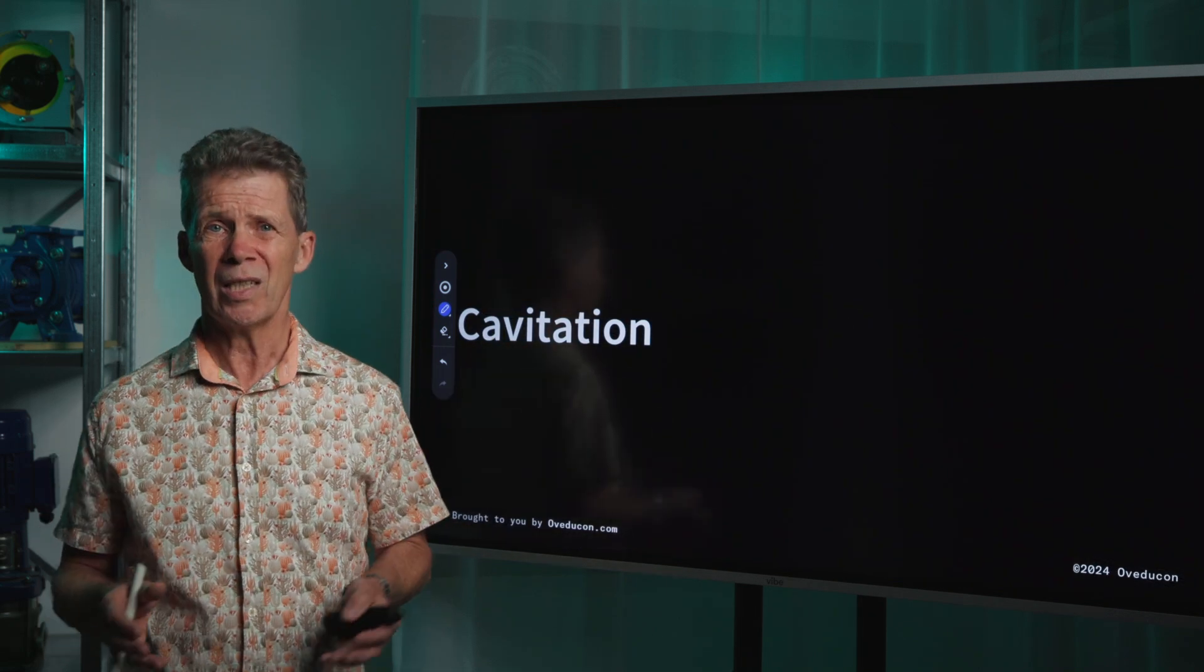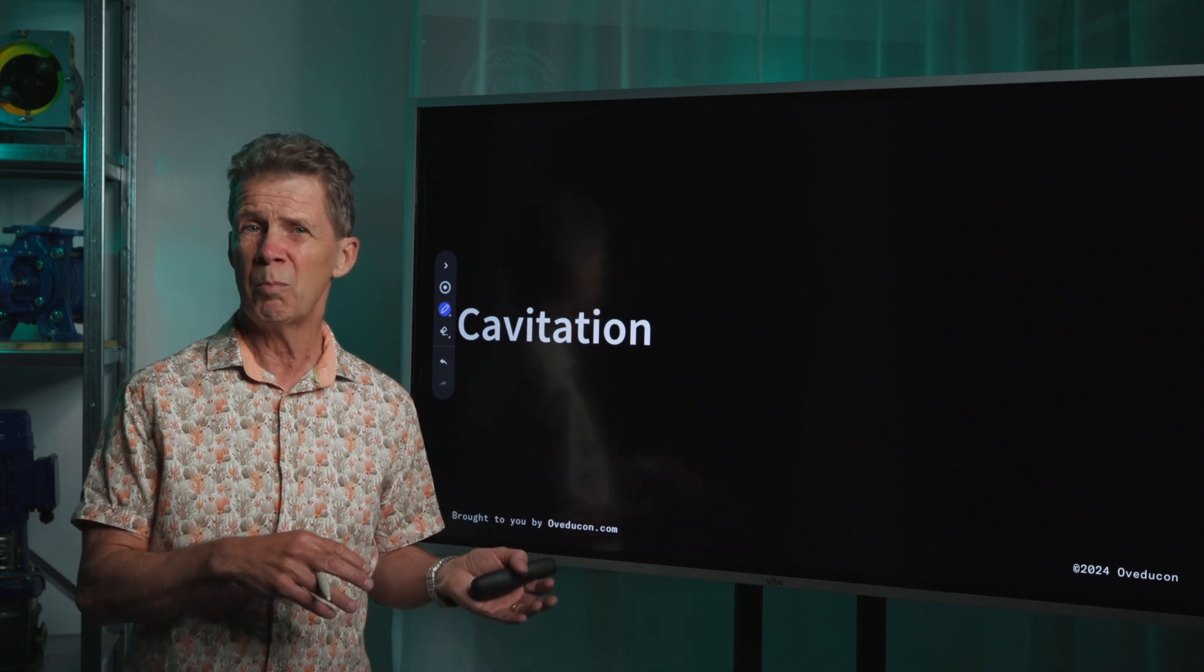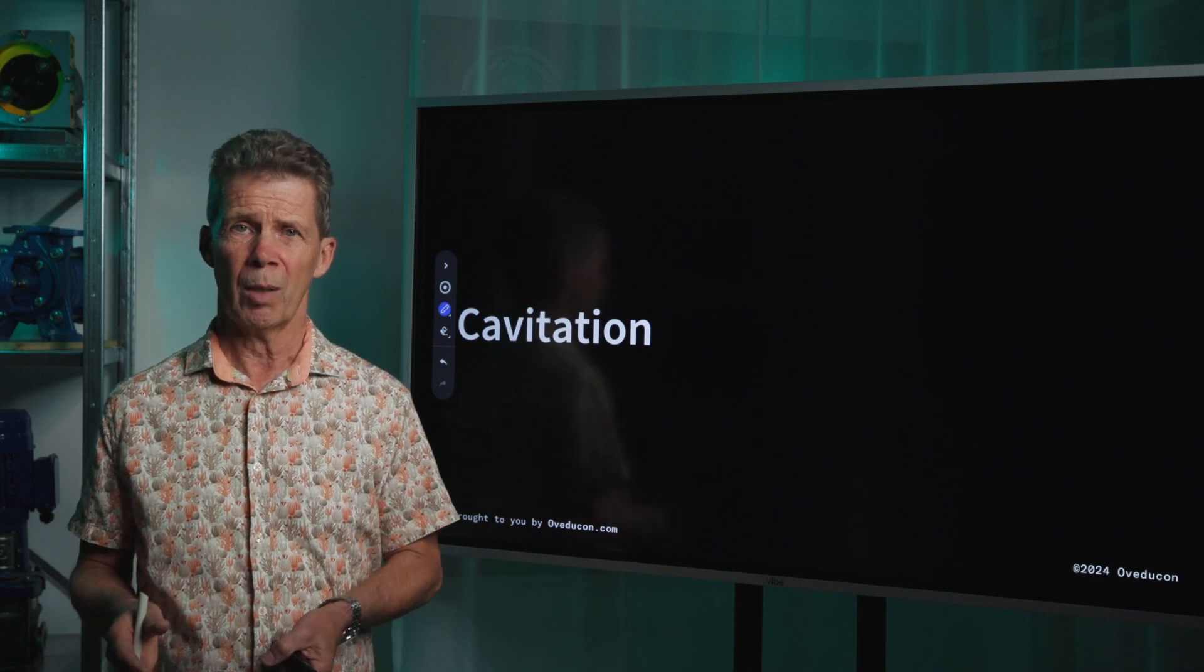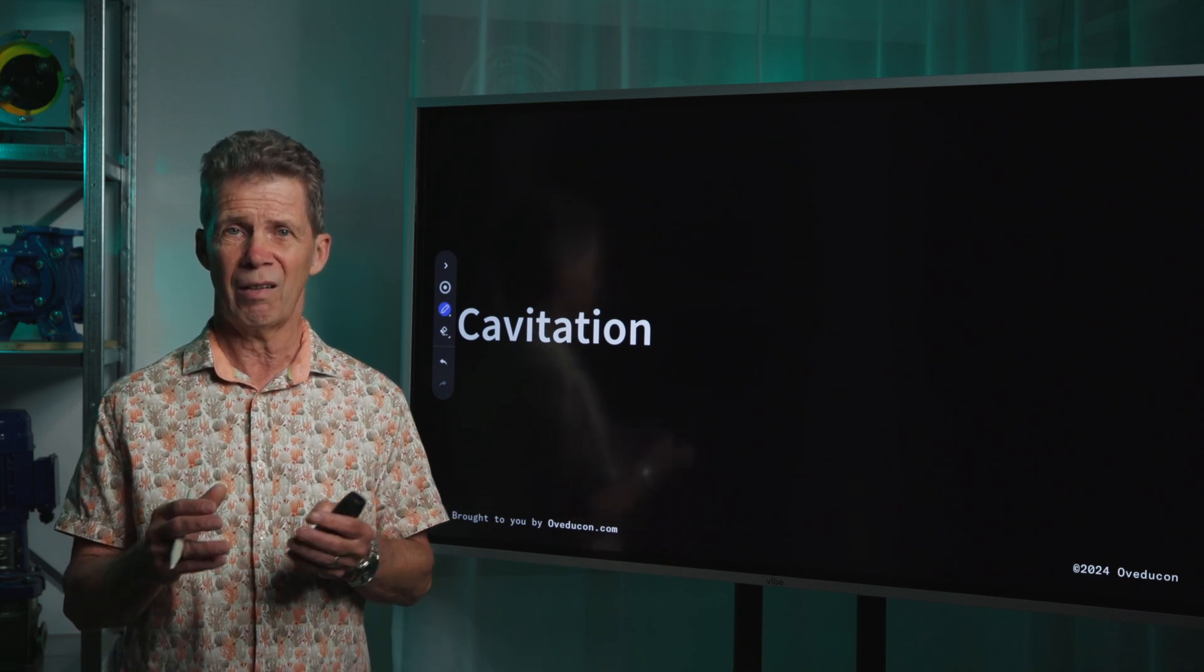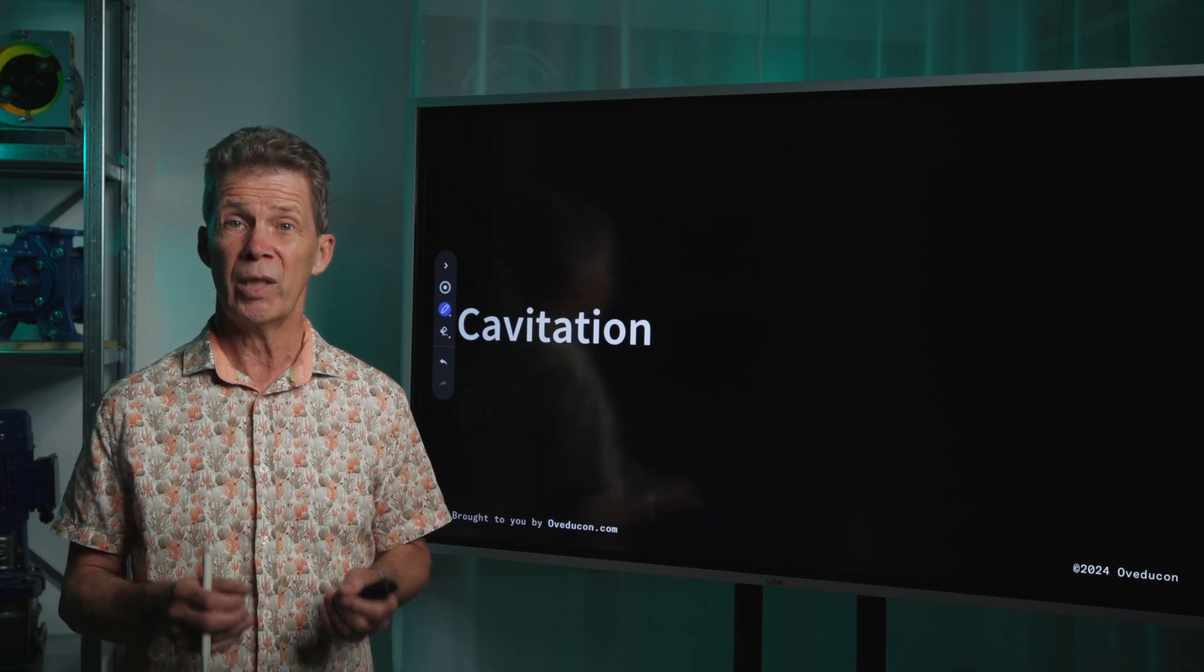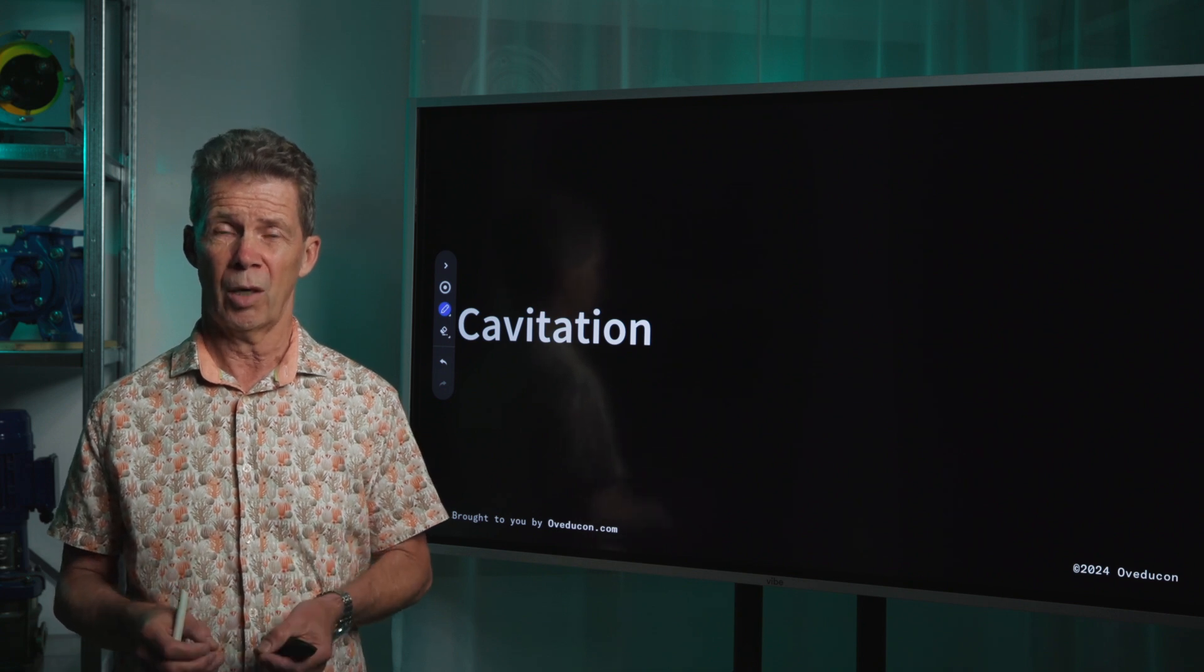Cavitation, what is it? I think you heard this buzzword a million times before. Cavitation is the implosion of vapor bubbles. The forces during the implosion of vapor bubbles can be between thousand and ten thousand bar. It can destroy your pump within weeks and it will always destroy the weakest part in your pump.